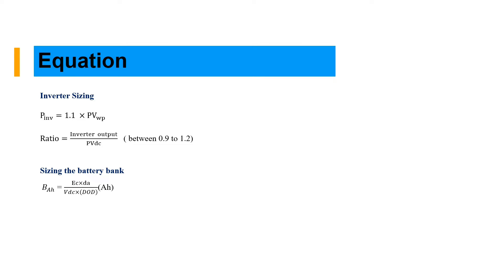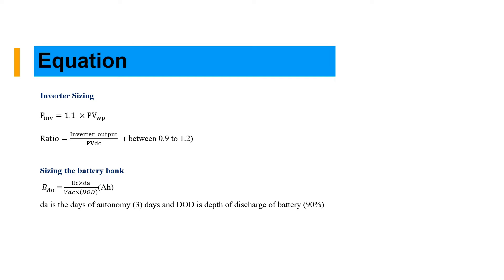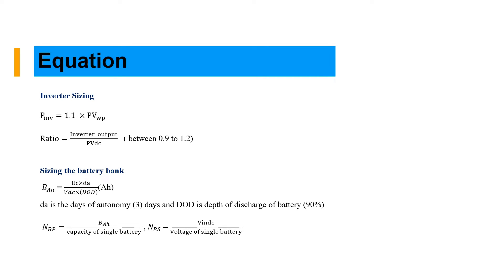Now we can size our battery. We can size by the energy consumption times DA times the DC voltage and depth of discharge. DA is the autonomy days, the days that you want your battery to supply without sun, in case of rain. Then we have how to size our number of batteries in parallel and series. The capacity of the battery divided by the capacity of single battery, and number of batteries in series is the V system divided by the voltage of the single battery.